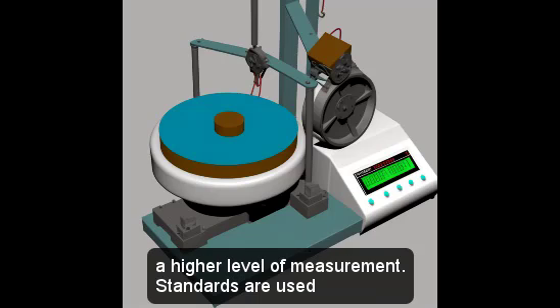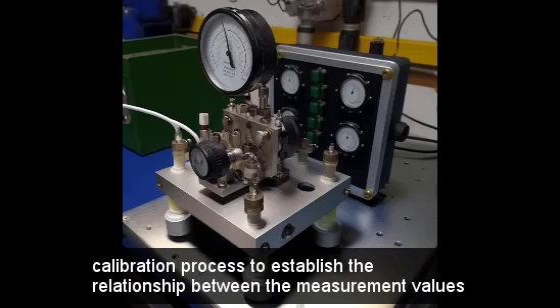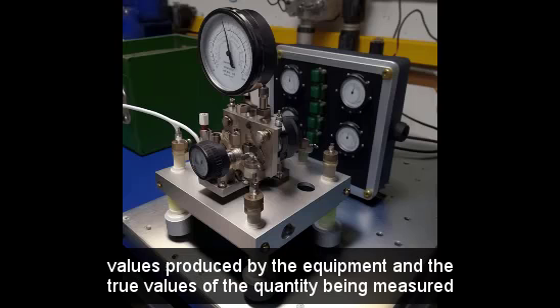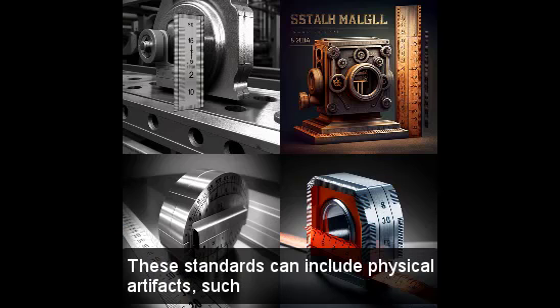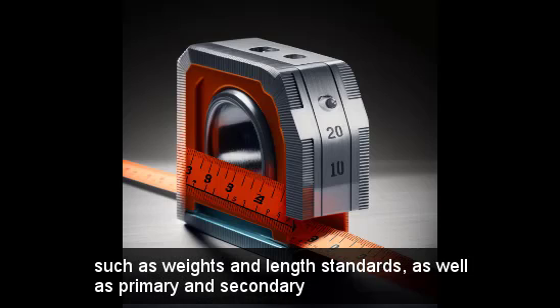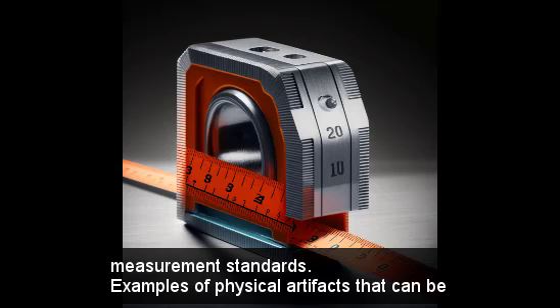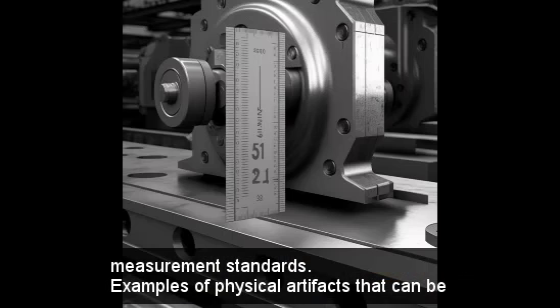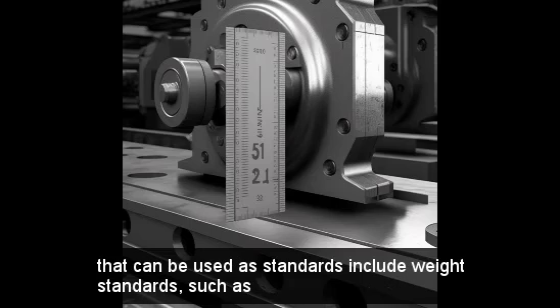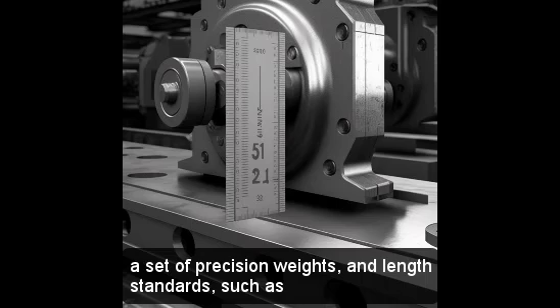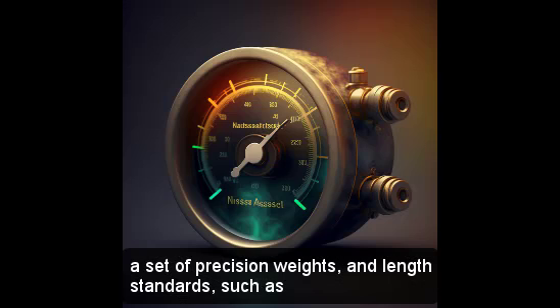Standards are used in the calibration process to establish the relationship between the measurement values produced by the equipment and the true values of the quantity being measured. These standards can include physical artifacts, such as weights and length standards, as well as primary and secondary measurement standards. Examples of physical artifacts that can be used as standards include weight standards, such as a set of precision weights, and length standards, such as a set of precision gauge blocks.